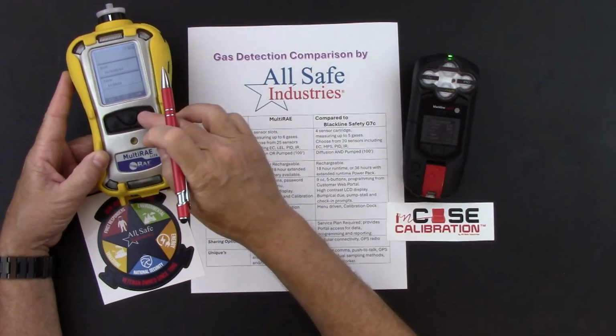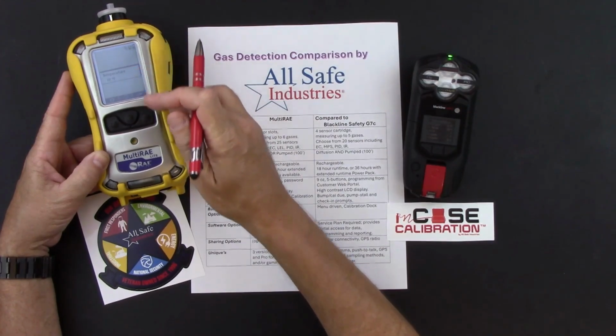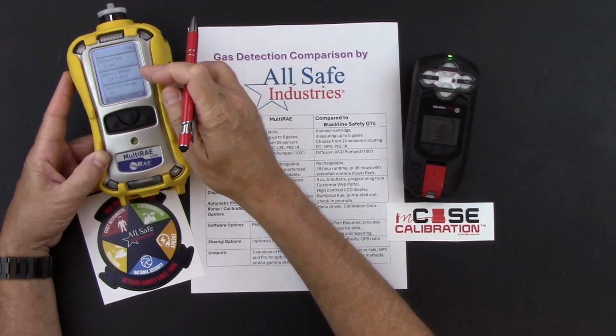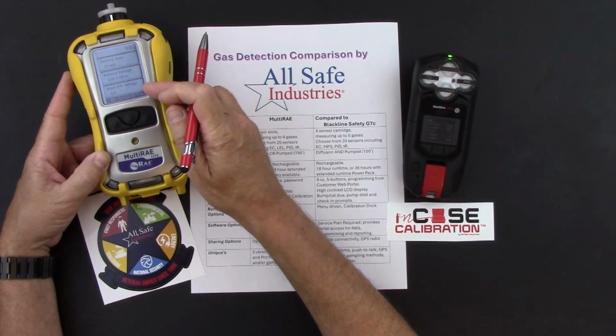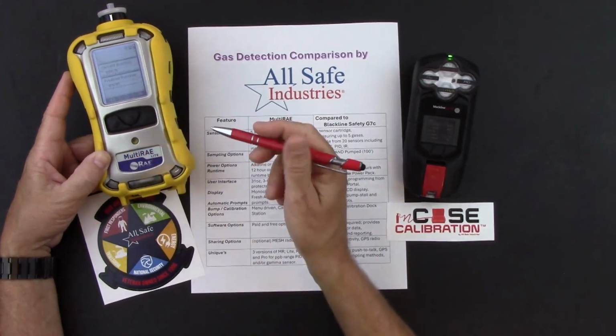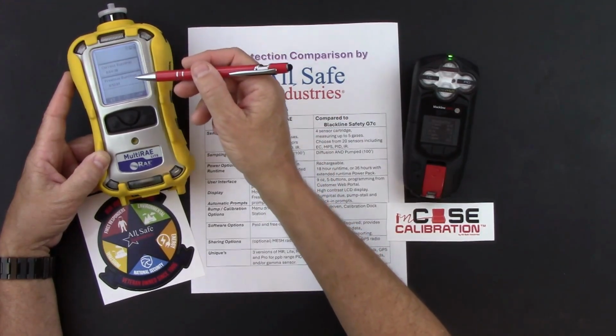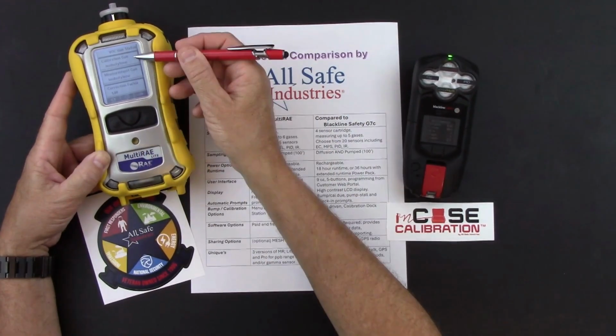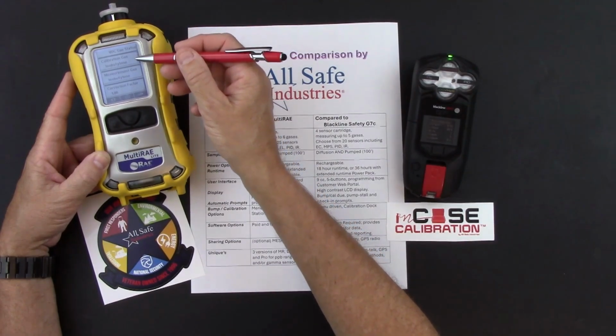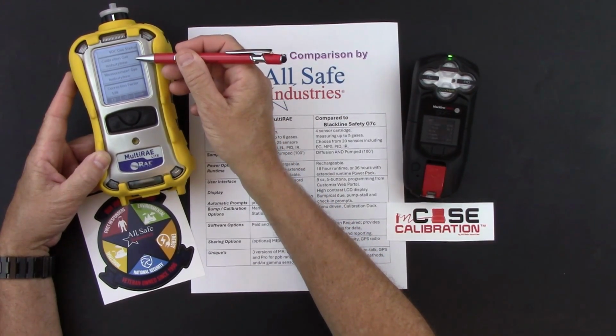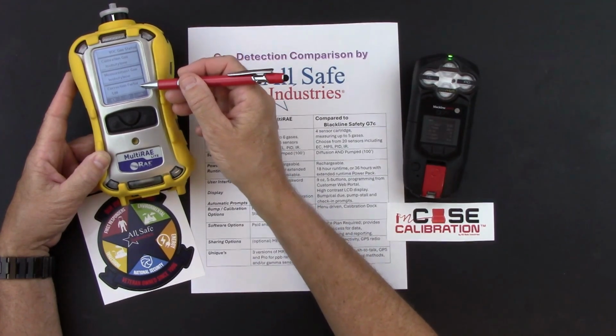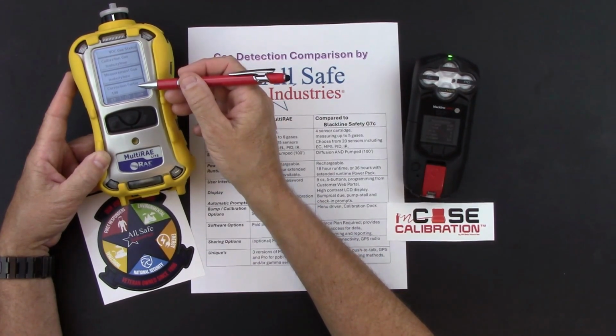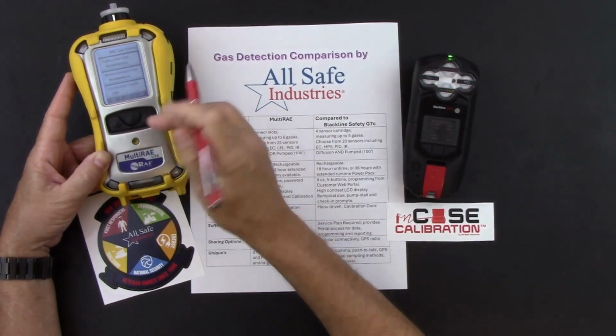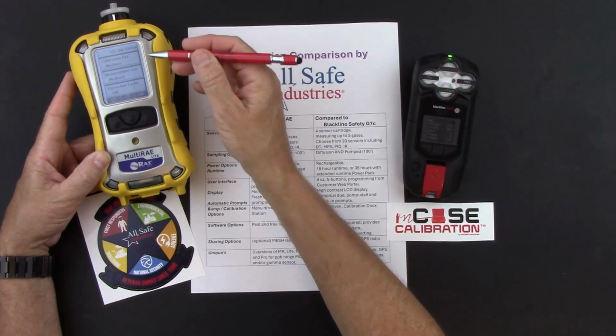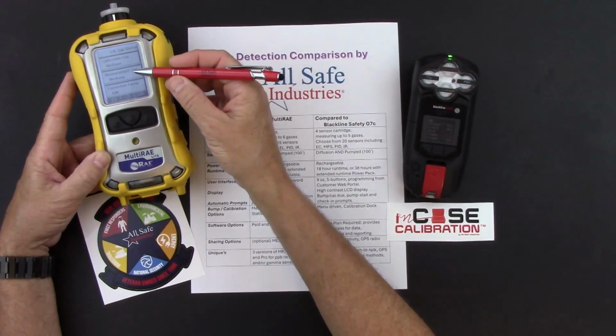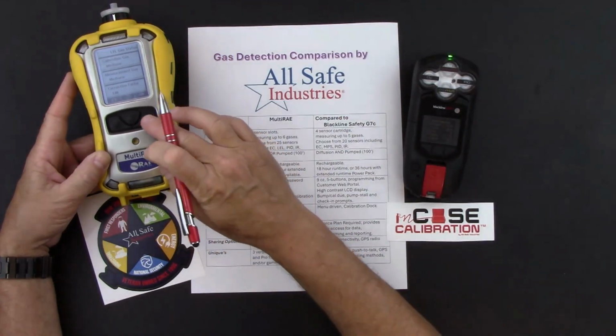My date and my time. My temperature readout. My battery type, voltage, and what percentage I'll be reading when the meter will begin its shutdown sequence because it's out of battery power. My current runtime versus my previous runtime. My VOC gas status page, which reminds me that my calibration gas I used was isobutylene. My measurement gas is isobutylene, therefore my correction factor is a 1. Any number times 1 is the same number. I get another screen for my LEL gas status. My calibration gas is methane, my measurement gas is methane, therefore my correction factor is a 1.